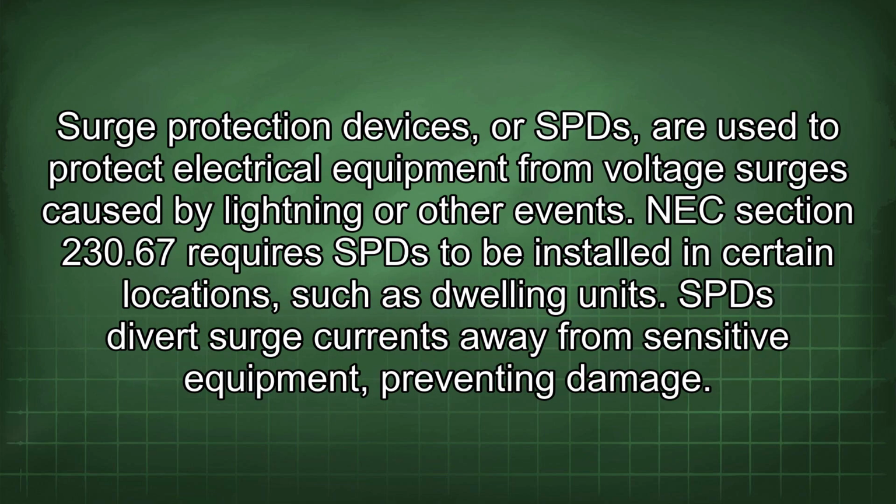Surge protection devices, or SPDs, are used to protect electrical equipment from voltage surges caused by lightning or other events. NEC Section 230.67 requires SPDs to be installed in certain locations, such as dwelling units. SPDs divert surge currents away from sensitive equipment, preventing damage.